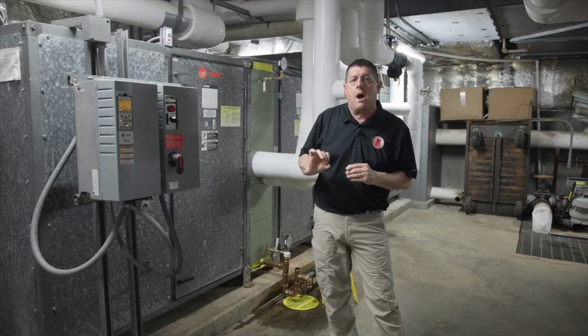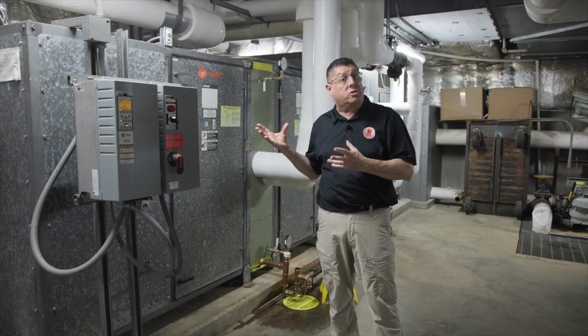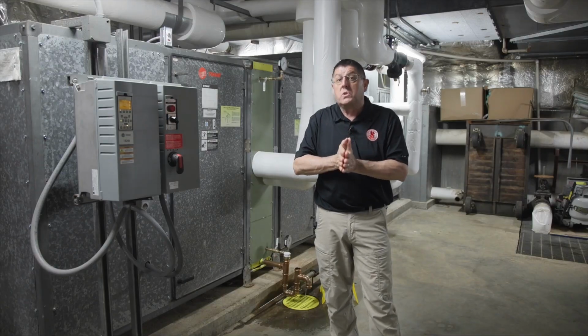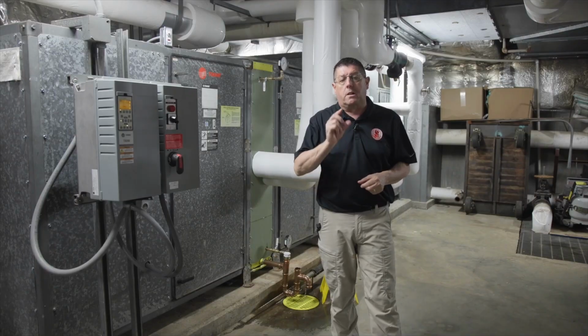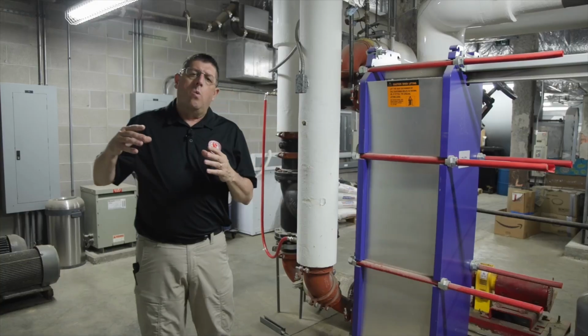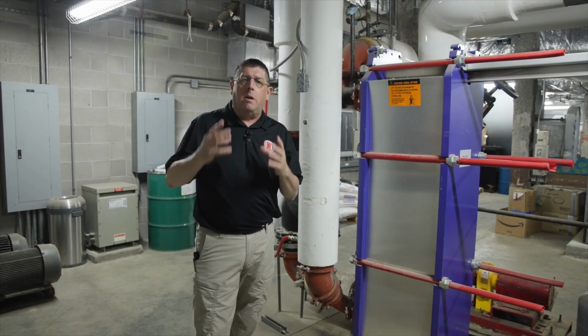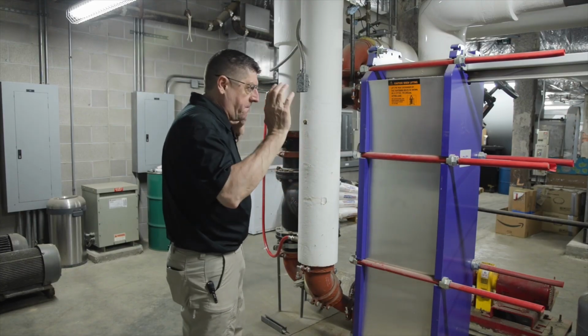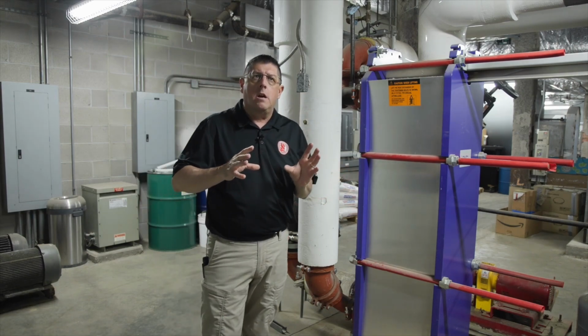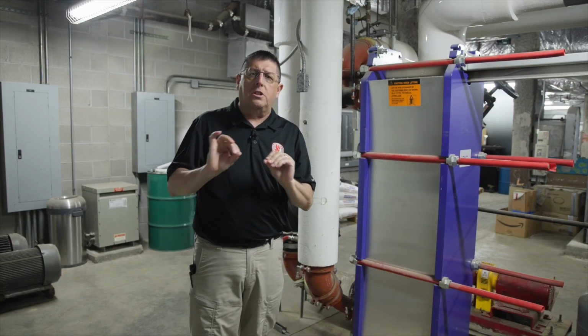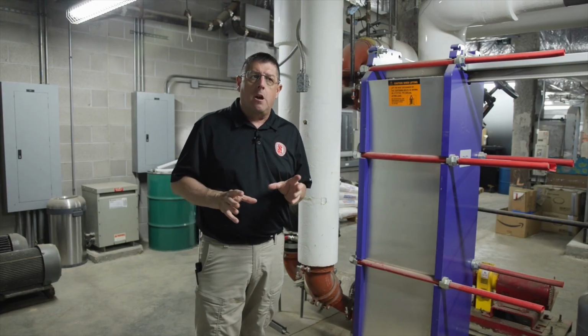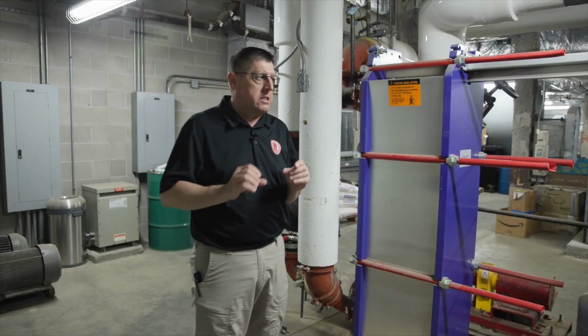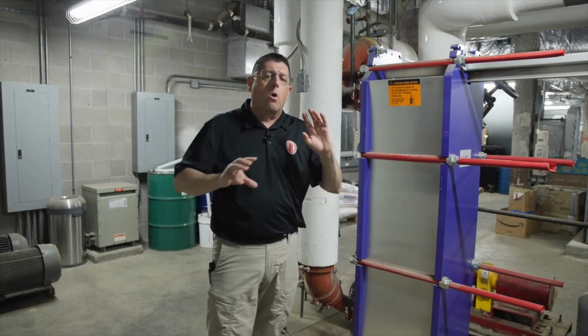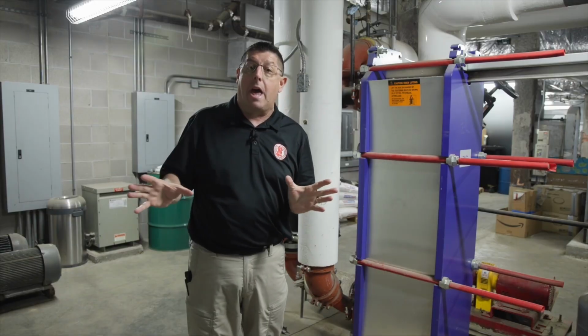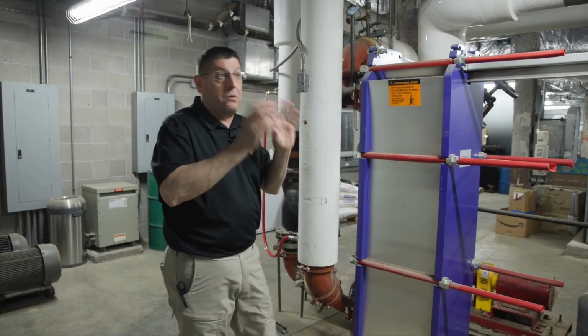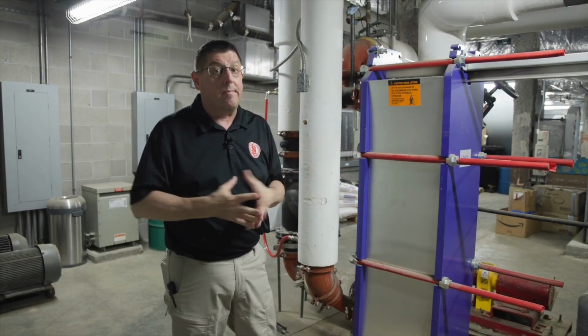But one unique feature that we have on this air handling unit, or the air handling units in this building, is a supplemental safety system to protect this unit called the glycol system, and let's look at that next. When you think of the pure expense and the millions and millions of dollars that are sitting in front of us, any hiccup or glitch in the system could render this catastrophic. And one of the things that could be very catastrophic is the ceasing or failure of either the heating or the cooling half of the system in a very cold atmosphere. And in that case, that could freeze the pipes and the system pretty quick.